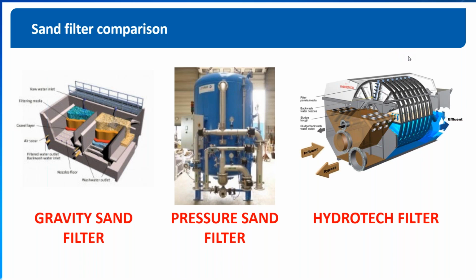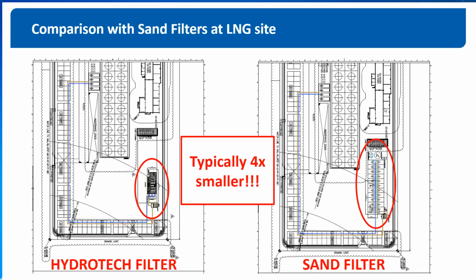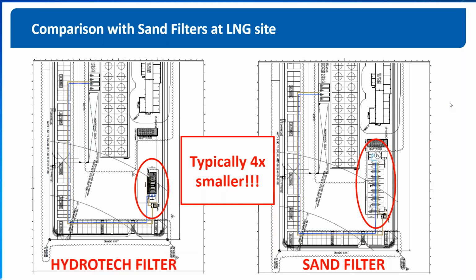Before I move on to the results, because I don't want to dwell on this point, I want to point out that one of the most interesting aspects is the size. For a given flow, the difference between a Hydrotech filter and a pressurized sand filter is typically that the Hydrotech filter will be 4 times smaller. The drawing that you're looking at is an installation drawing for an oil and gas site, but it is a valid principle.